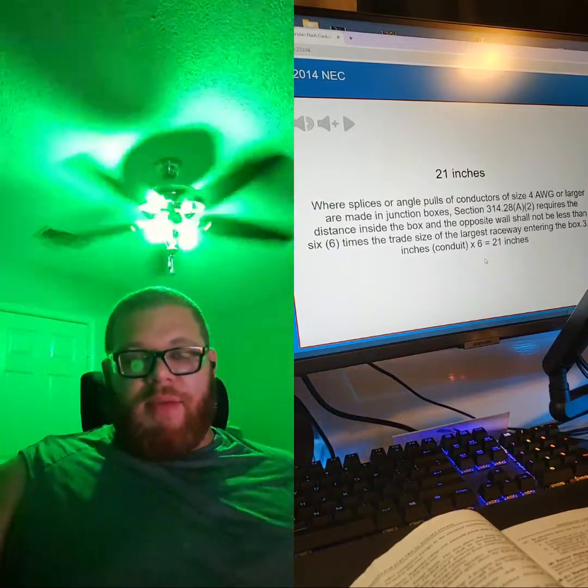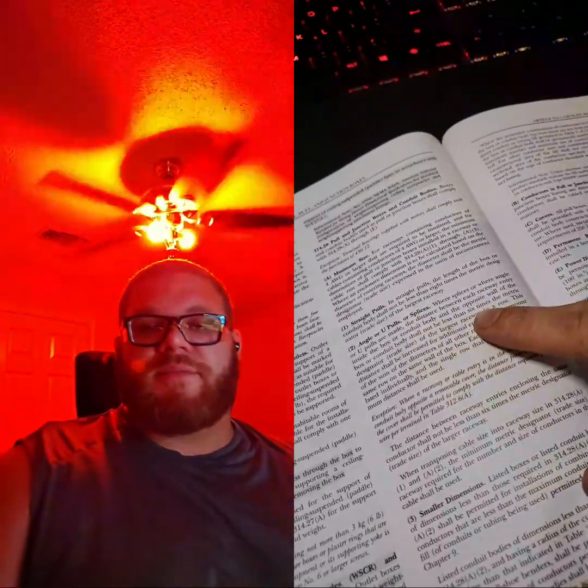But if you don't know, you go to 314. So if we go here to 314, right here, and we go to straight pulls right there, or angled U pulls, and then you've got 6 times right there. And that only applies to conductors that are number 4 or larger. So that's how you do that.